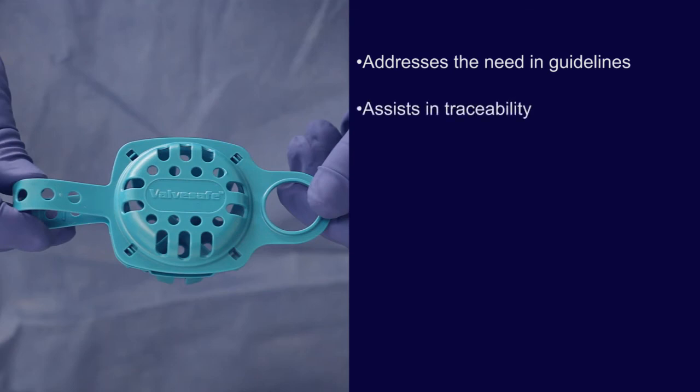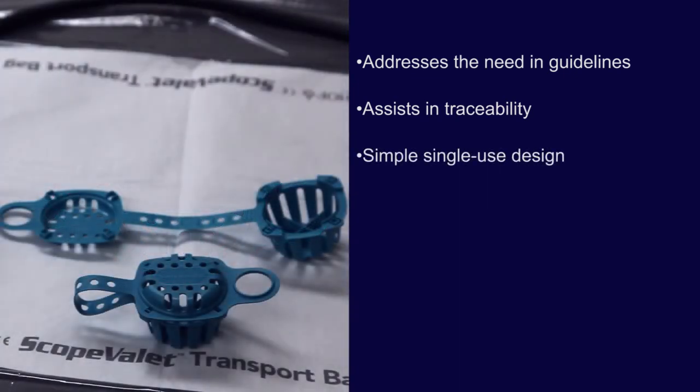ValveSafe assists in the traceability of the scope and its valves. It's a simple, single-use design with large opening apertures allowing adequate disinfection to pass through during the AER process. The ValveSafe helps protect the valves against damage during the transportation and cleaning phases and is also CE marked for medical use.